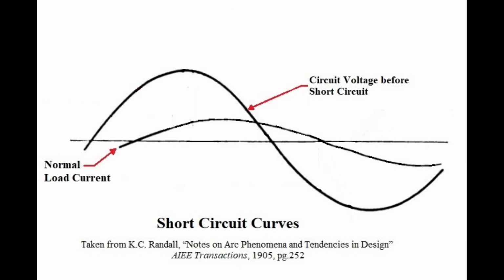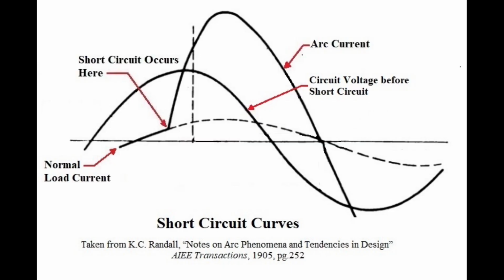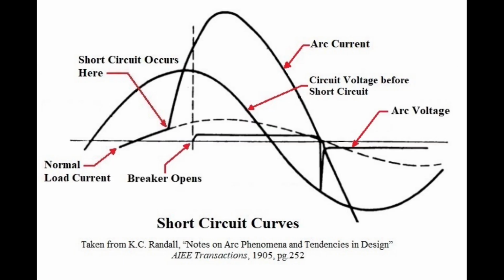Shown here is the normal voltage and current relationship before a short circuit occurs. The following sequence is intended to give some insight into what engineers were up against before they could see these complicated events that occurred in such a short space of time, from between 2 to 4 milliseconds. Although this diagram may seem complicated, it is an oversimplification of what is actually happening in the circuit. When the short circuit occurs, the impedance of the circuit is reduced dramatically, resulting in a large arc current. The breaker opens and an arc is drawn between its opening contacts.